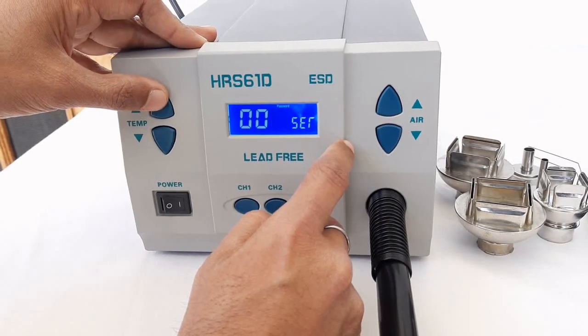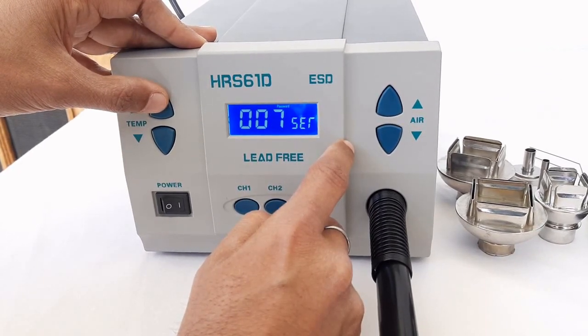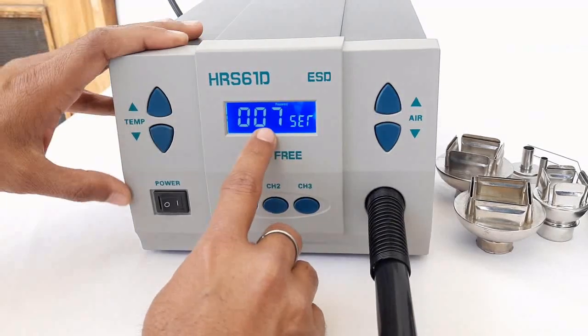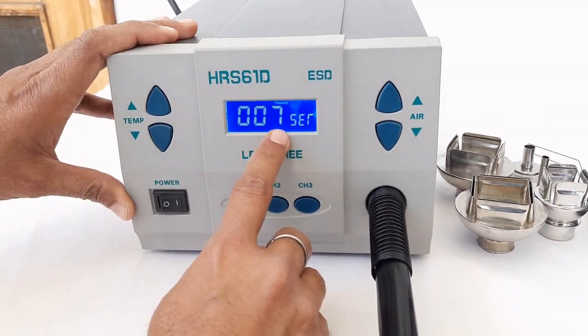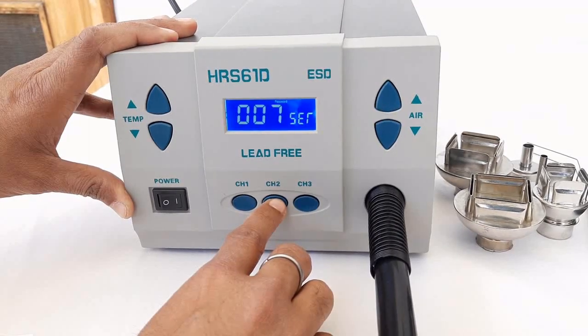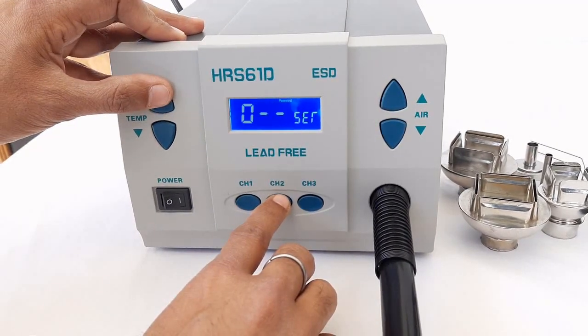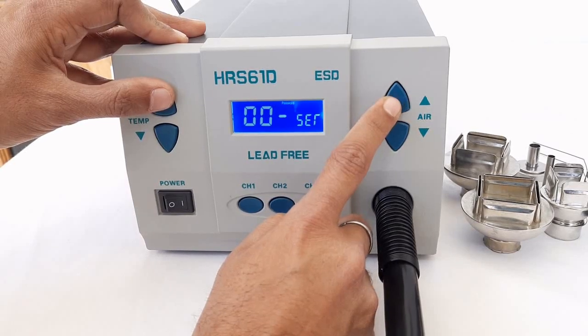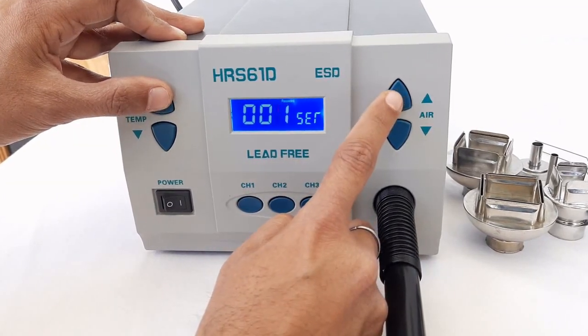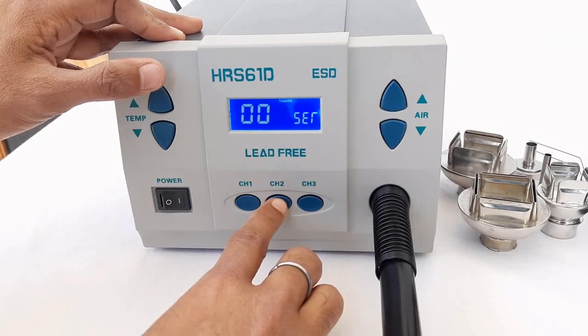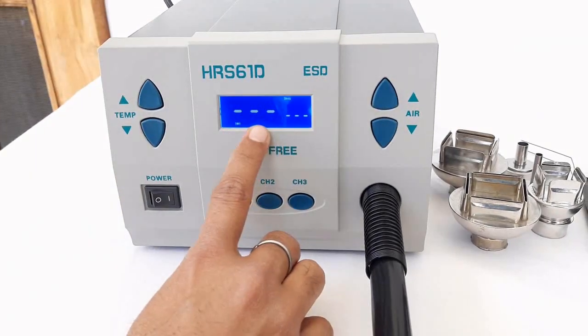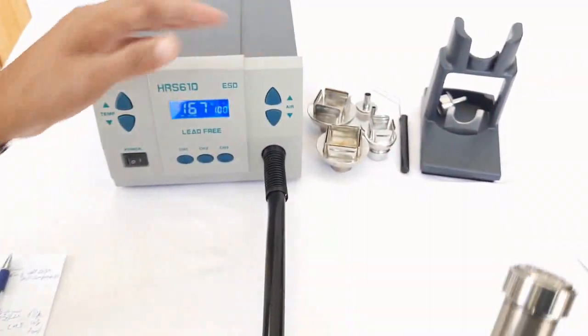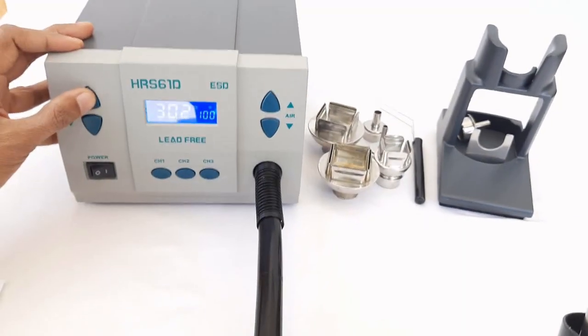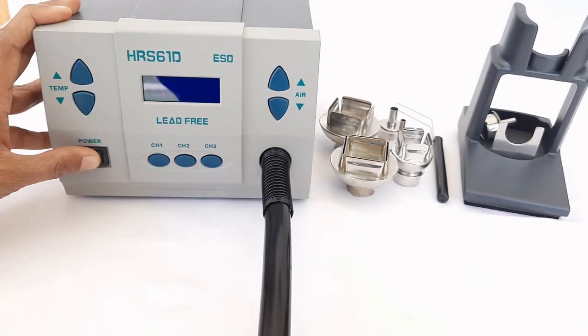Then we will use 7. So we have entered the password of our own choice. Then we need to press this channel 2 button once again and repeat the process, and press channel 2. Now the password has been changed to 0007, and we will show you that now the password locking is enabled. But first we need to switch the unit off, and switch it on.